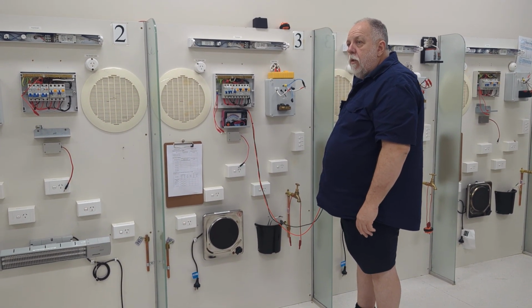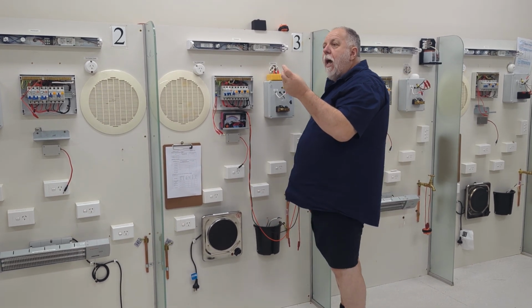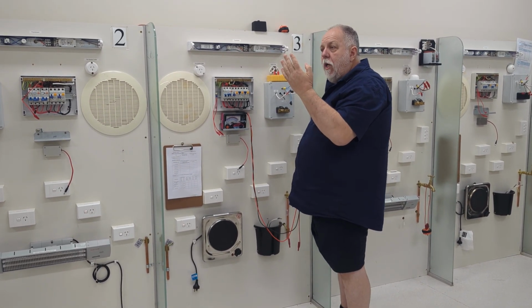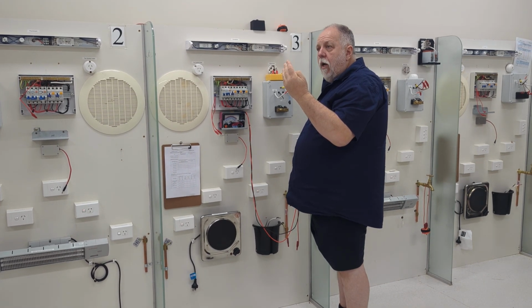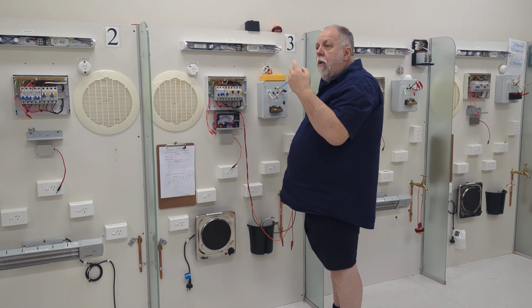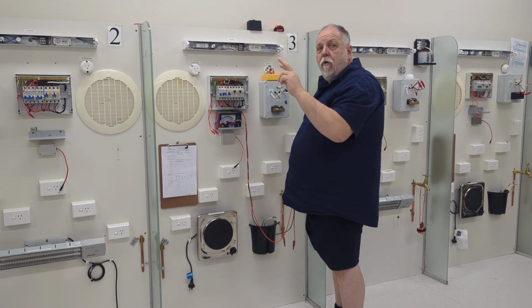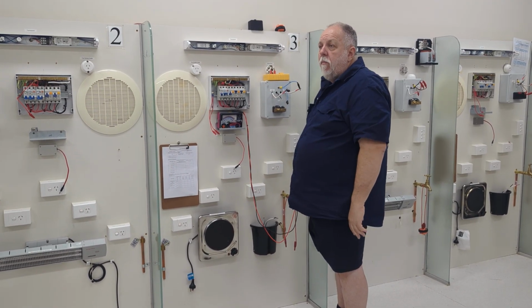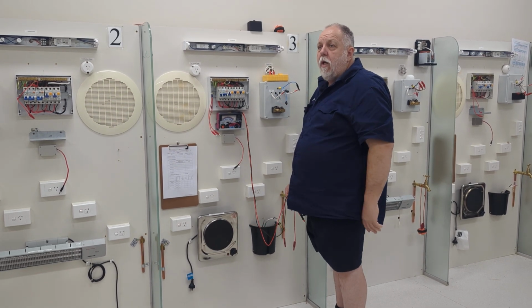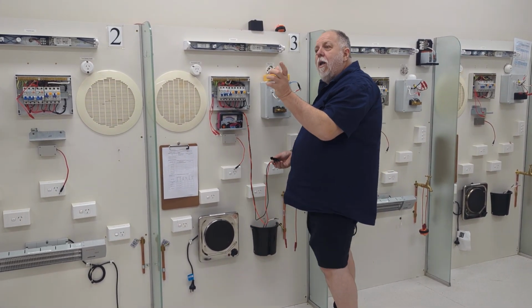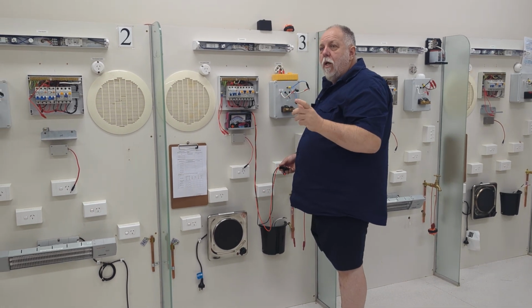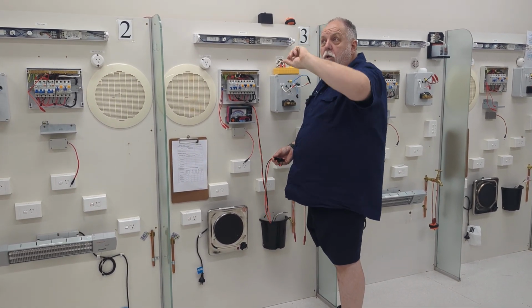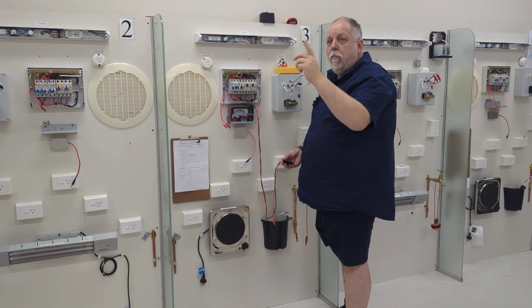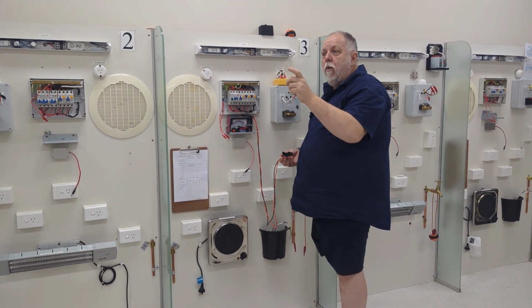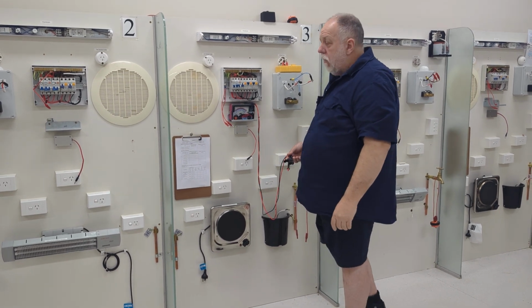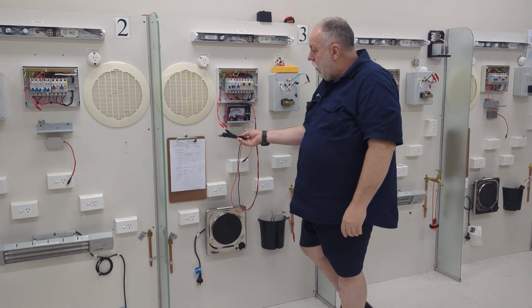All right, no problem. Especially on the 3-phase circuit, the blue and the black, especially if you're running 4 black SDIs, XLPE, it's quite often I've seen where the neutral and the blue phase have been swapped. So that's why you've got to make sure you've got the consistency of everything going out from A to B. And that's why they insist on putting colour or heat shrink on all your cables. Do you understand what I'm getting at? Especially if you go through a brick wall or somewhere like that. I used to put heat shrink through so we could identify the cable from one side to the other. It's amazing through 100 mil of wall how something can get crossed over. All right? Done the mains.